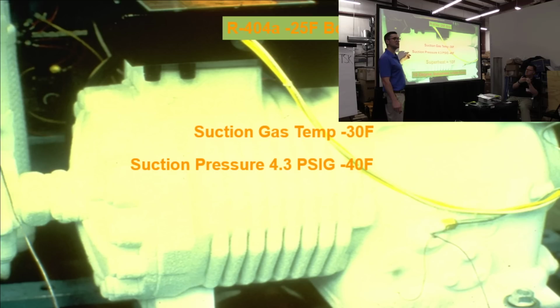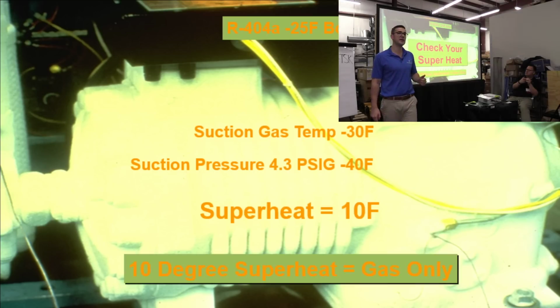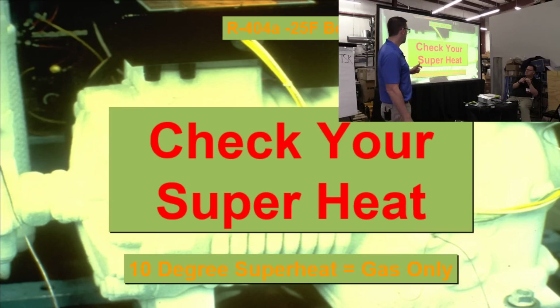No, it's not. 10 degrees superheat. Check the superheat. So I walked into a store one time, and every compressor, there's 5 of them on this rack, and they were frozen. There was 4 inches of ice on them. My heart was pounding because the whole store was down. I'm like, oh my God, there's something wrong. All these compressors are done.